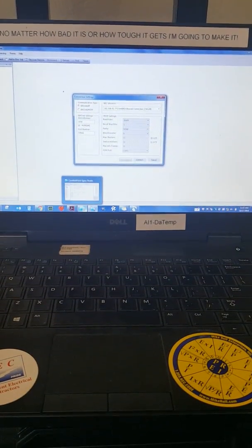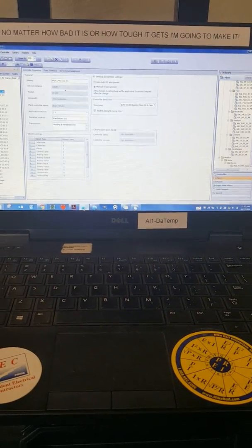CP-SPC controller right here, and right now the way I'm downloading to this device is through an MSTP converter. Normally with the plant controllers like the Honeywell CP-06A, I can communicate via Ethernet, but now I have to go from Ethernet to MSTP. I've got power coming from something like a printer cable and the Ethernet connection right here, and the MSTP comes on a 2-wire small bus down to the RS-485 connection on the device itself.